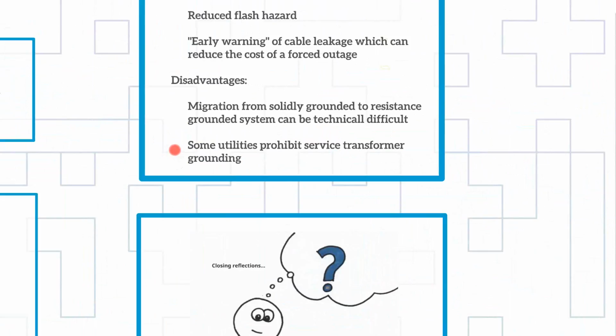Let's say you're doing infrared detections, which says I got to do it hot. So you put your PPE on, you open the back cover of the switchgear, you stand back 3 feet or whatever distance with your infrared camera. Anything happens in that case, 80% of the probability says it's going to start as a single ground fault. And that's going to be a mere fraction of the energy, and you have time to get out of the way. So it's going to improve the safety. You still have to have your PPE on to do the 3-phase or whatever, but it's going to actually dramatically improve your safety for the people, too, for the few times you have to get it exposed.